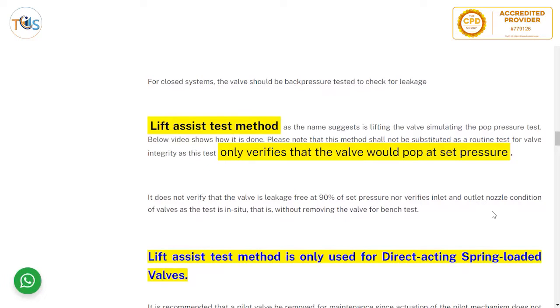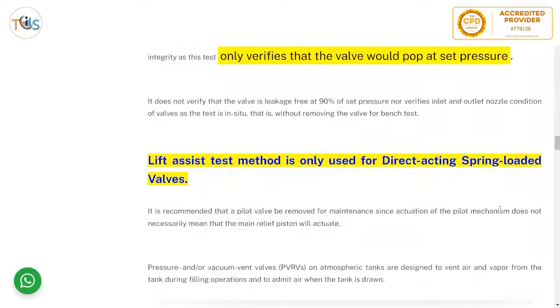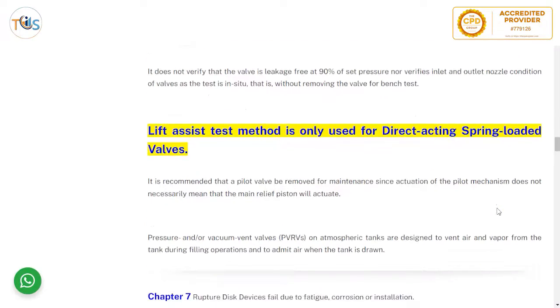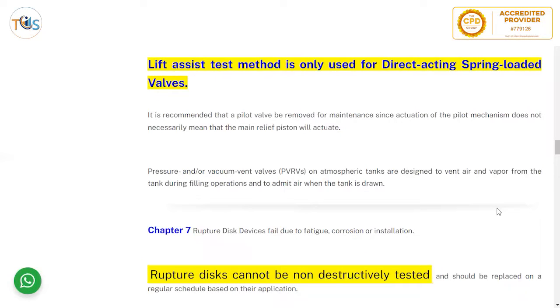For a closed system the valve should be back-pressure tested to check for leakage so there is no backflow of fluid. The lift assist test method simulates the pop pressure test by lifting the valve. Note that this method shall not be substituted as a routine test for valve integrity, as it only verifies that the valve pops at set pressure. It does not verify that the valve is leakage-free at 90% of set pressure, nor does it verify inlet and outlet nozzle condition, since the test is in-situ without removing the valve for bench testing. The lift assist test method is only used for direct-acting spring-loaded valves.